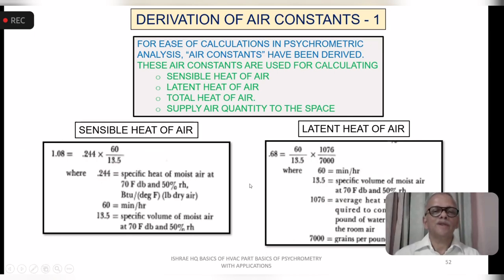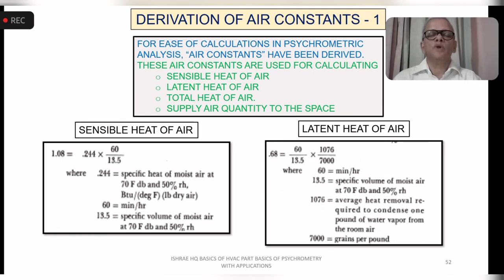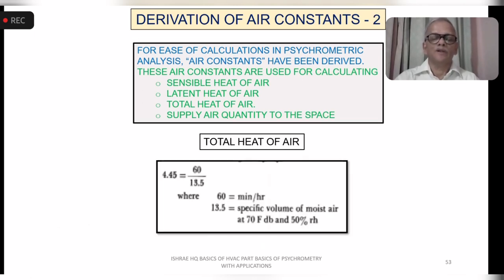Why I have repeated it is because here the concept is different. We are saying that I will be supplying this air at this dry bulb and humidity or moisture content, and then I am supplying so much air quantity as CFM or air flow rate. I know the room loads, sensible and latent, and then I have computed the resultant room condition. It is the opposite of the design, just to validate or verify whether with this system I will be able to achieve the desired results or not. This is for the total air, which you have seen before.